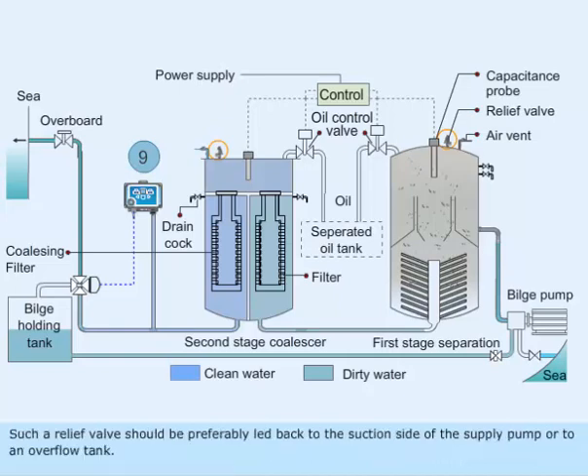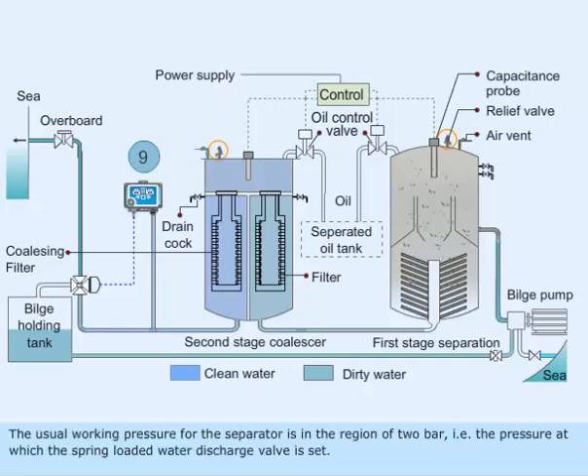Such a relief valve should preferably be led back to the suction side of the supply pump or to an overflow tank. The usual working pressure for the separator is in the region of 2 bar, which is the pressure at which the spring-loaded water discharge valve is set.